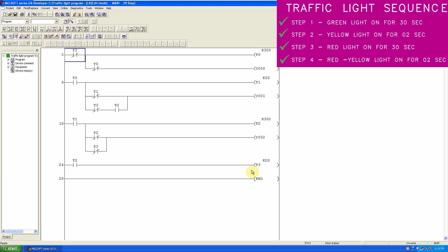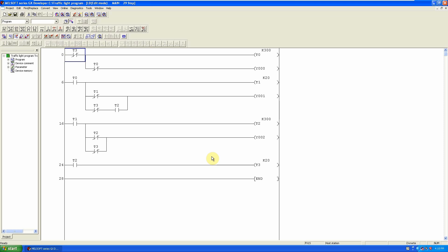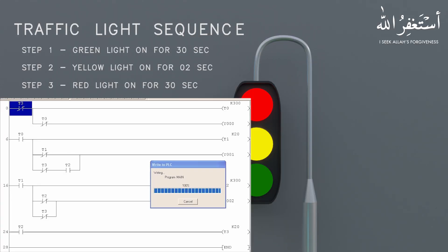One last thing remaining is that we have to reset the timers so that the program can restart its cycle. To do this, we place a normal close contact of timer T3 in the first rung. Once the last timer T3 is over, it will open this T3 normal close contact in the first rung, reset the complete logic, set all timers back to zero, and start the program all over again as long as the PLC is powered on. Let's upload this program and see how it works.